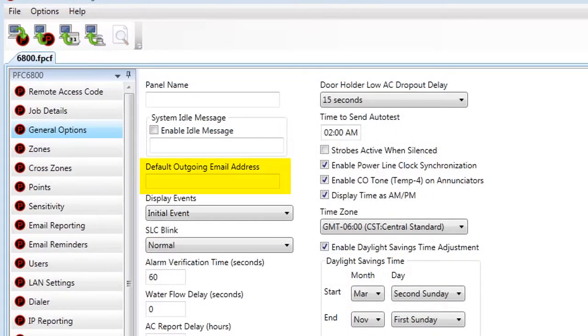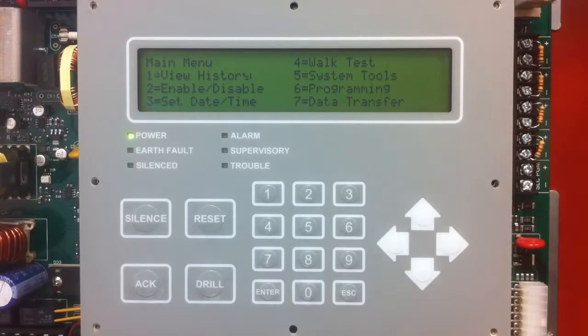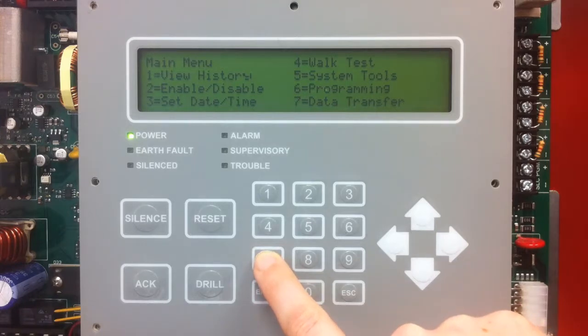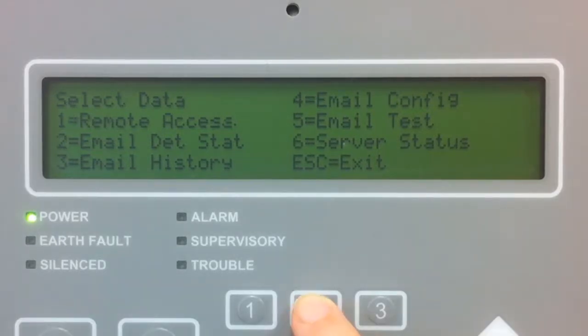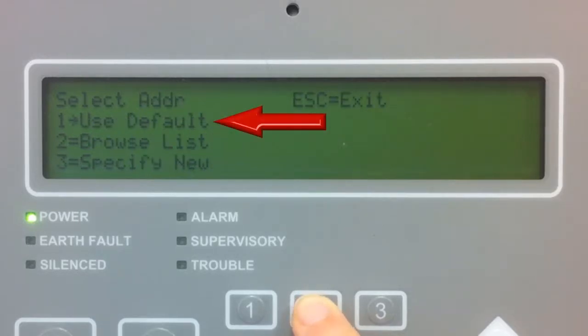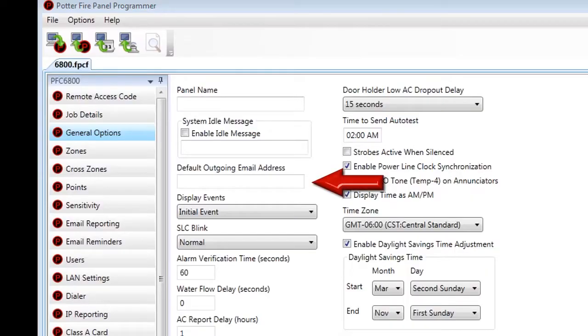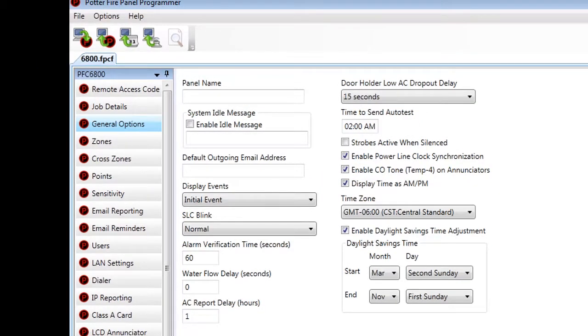Underneath the System Idle Message is the Default Outgoing Email Address. Here you can enter an email address that can be accessed through the keypad of the fire alarm control panel in the Data Transfer menu. Under option number seven, you can select to send detector status history, a test email, or the configuration file — and in any of those options you can choose to send it to the default outgoing email address as programmed in this box.